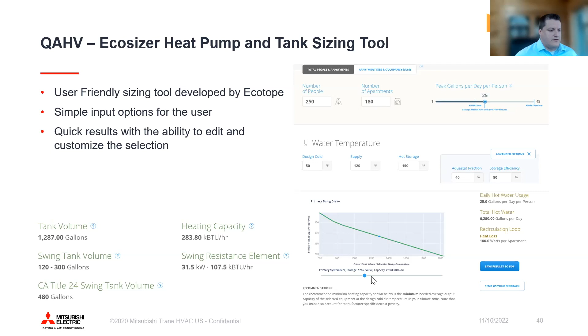Then it gives you an output - this example shows 1,200 gallons and 283 MBH. What you can do is use this slider to basically depict how much plant versus storage you want to fit in your actual mechanical room or building. So you can put some conservative nature in here if you want, or look at really sizing, downsizing the storage as much as you see fit.